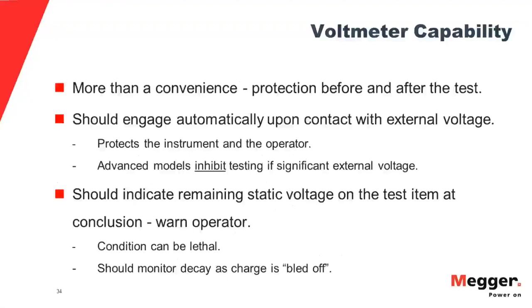Now, voltmeters. We pointed a few slides back to the voltmeter capability when it started to be added into insulation testers. For one thing, it's a convenience. It saves you from having to go get another unit and hook it up if you want to know what the voltage is. So it's a nice convenience. But far more important is the safety function of a built-in voltmeter.